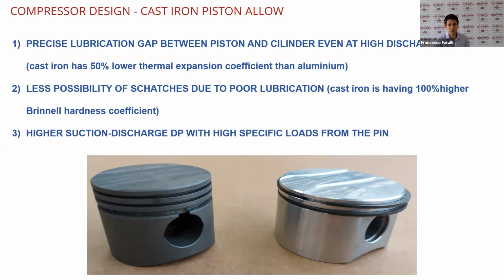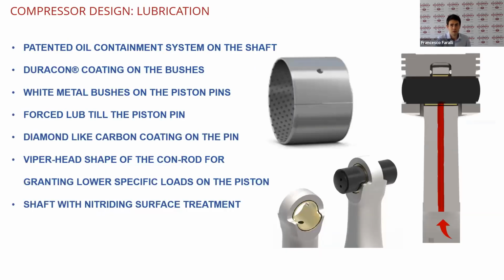In the other case, what you risk is that the piston made of aluminum will expand a little bit more than what the crankcase in cast iron does. And so the tolerances between the piston and the cylinder will not be as the nominal values. Then for the models with the oil pump, we have a new patented, as I said, oil containment system. And then I'm going to show you just a little bit more in detail how it works.